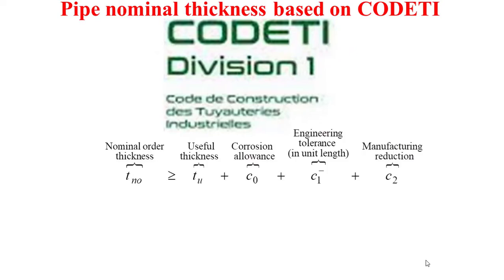CODETI states that the nominal order thickness of the pipe should be no less than a certain useful thickness plus a corrosion allowance, plus an engineering tolerance in unit length, plus a manufacturing reduction.